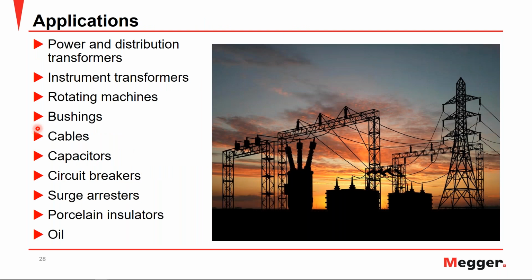Now we've been talking about transformers, but I'd like to just take a slide to talk about the different applications for power factor, because it's not solely just for transformers. It can be used for power and distribution transformers, but also for instrument transformers, rotating machines, bushings, cables, capacitors, circuit breakers, surge arresters, porcelain insulators, and oil itself. So power factor has many applications, but for this presentation, we're going to focus on transformers.